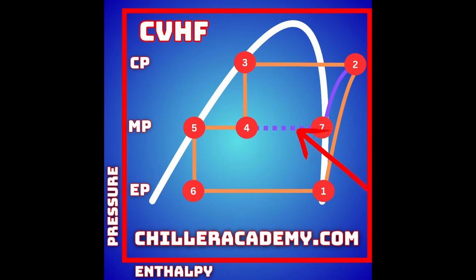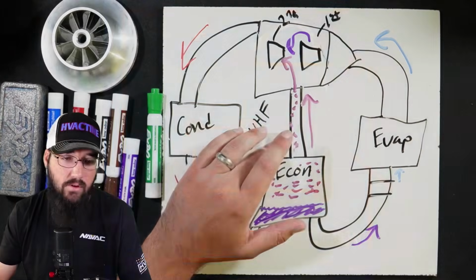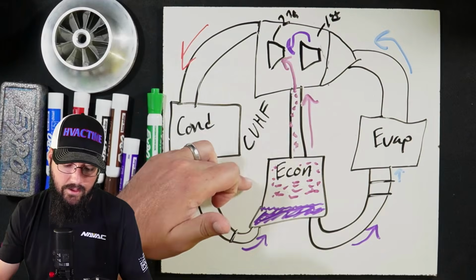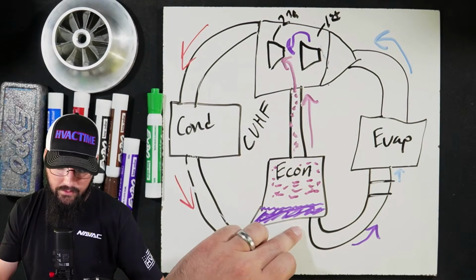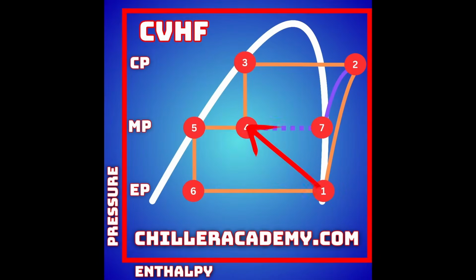The economizer, by removing that flash gas, has removed all of this heat right here between 4 and 5. That heat that was here goes right here with that flash gas. And that is part of what this flash gas is doing. It is carrying that heat away so that we have a lower enthalpy. And that's what this chart is showing you, is our enthalpy reduced. Our pressure didn't. Our enthalpy did. So now this liquid refrigerant can handle a lot more heat to be put into it than it could have handled if we didn't send it through the economizer.